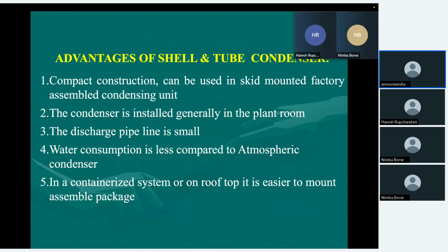What is the advantage of shell and tube condenser? Now there are many types of condensers. Mostly we use evaporative condensers also, but there are certain advantages of shell and tube condensers. It is a compact construction and can be used in skid-mounted, factory-assembled condensing units. For example, a lot of people are now manufacturing ammonia units and putting them into mobile containers. In that container, you can use shell and tube condensers, which is more convenient than other types of condensers.